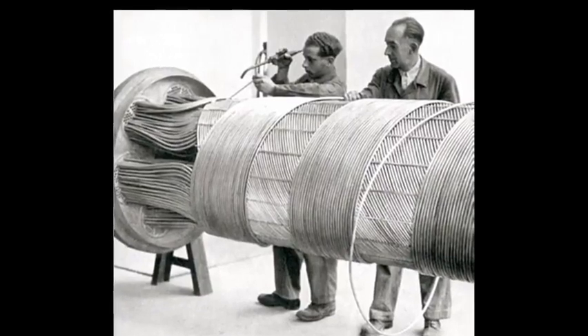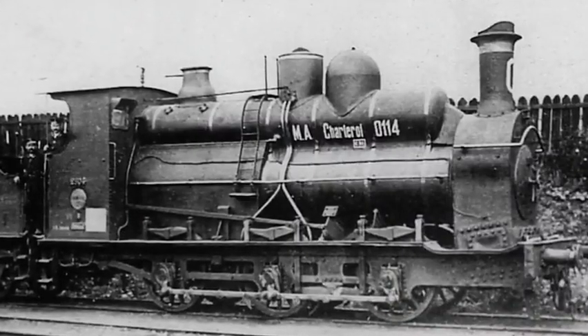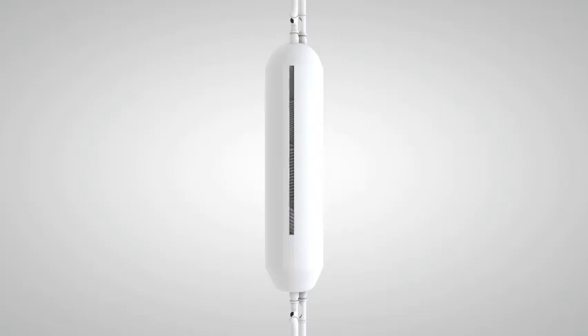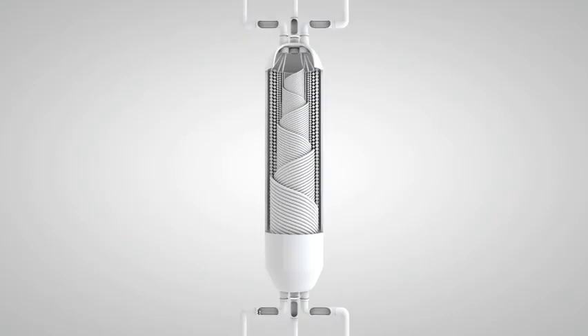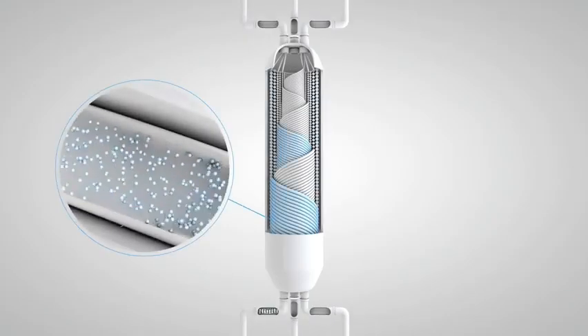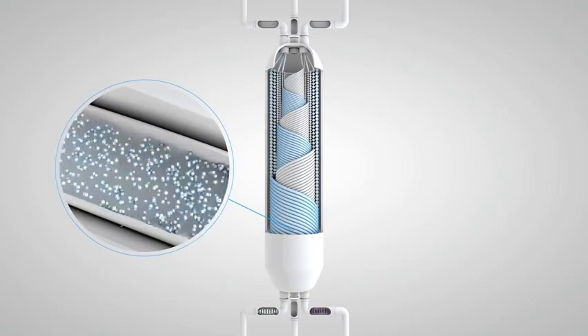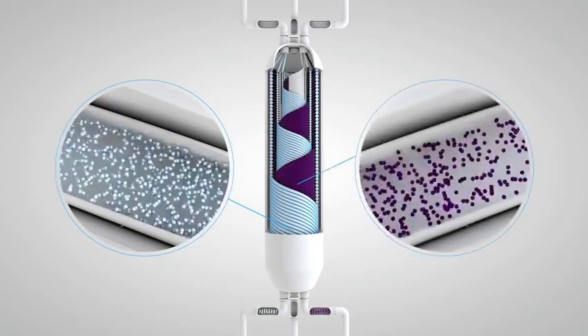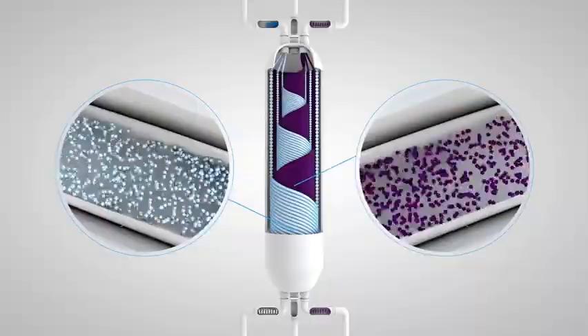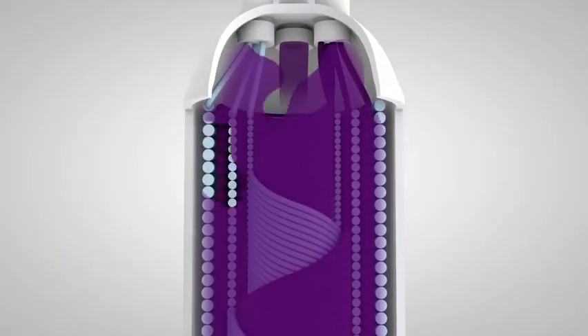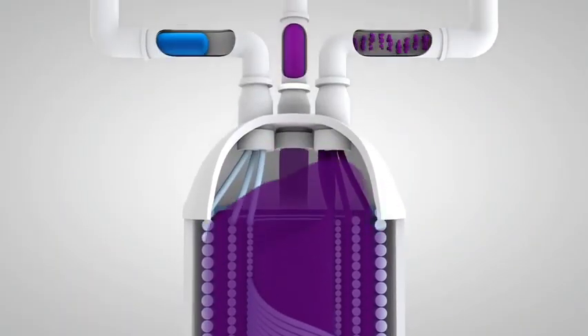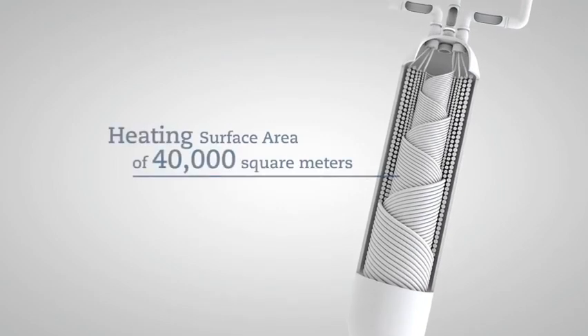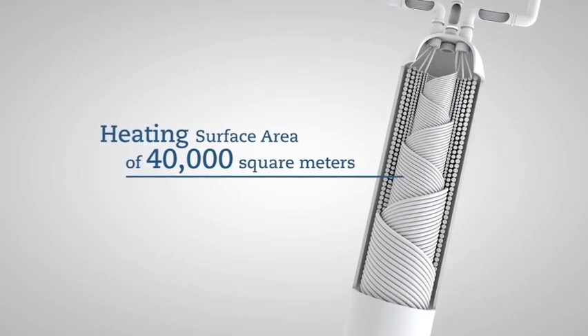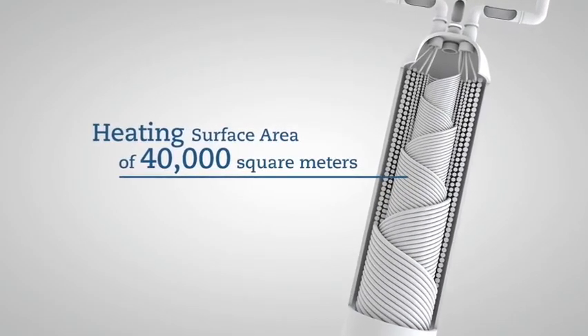Coil-wound heat exchangers have been around the longest. They evolved from 19th century locomotive boilers. Today, we wind multiple layers of tubes inside a pressure vessel shell. Natural gas and high-pressure refrigerant both cool as they flow up inside the tubes. Very cold refrigerant flows down around the tubes in the shell. Those wound tubes can provide a heating surface as great as 40,000 square meters.